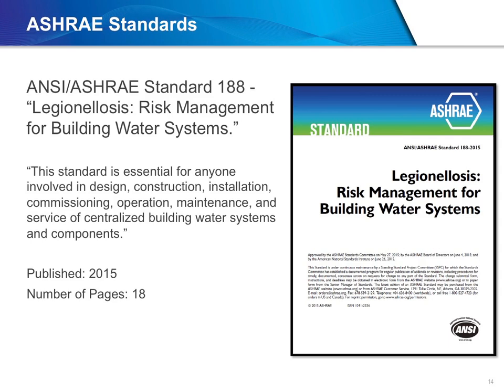This standard, which they suggest is essential for anyone involved in design, construction, installation, commissioning, operation, maintenance, and service of centralized building water systems and components, establishes minimum risk management requirements for building water systems to combat the Legionella bacteria. It not only includes a description of the environmental conditions that promote the growth of Legionella, it also outlines action plans for managing and monitoring those conditions. Additionally, there are informative annexes and a bibliography that contain suggestions, recommendations, and references for additional guidance.